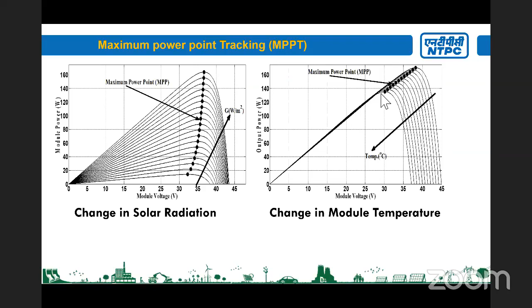In the earlier inverters, maybe in 2016 and later, we generally used a two-level inverter. The two-level inverter is basically a 6-device configuration, and these inverters are generally for 1000 volt DC applications. Initially we had a 1000 volt PV system, the inverter DC voltage was 1000 volt maximum, and the rating of the inverter was in the range of 1 megawatt to 1.25 megawatt.